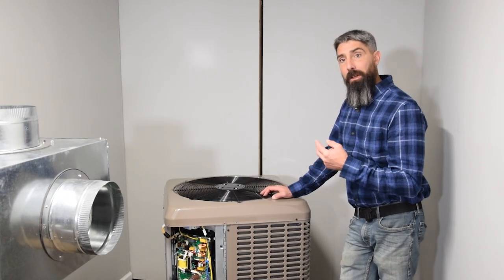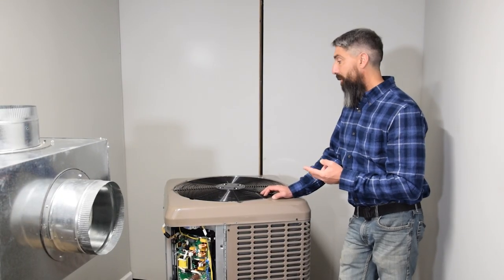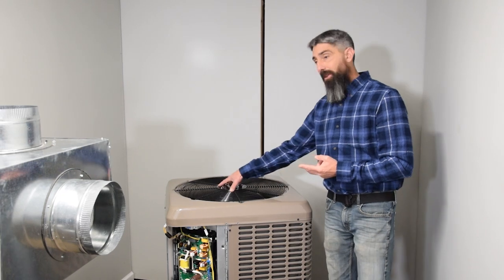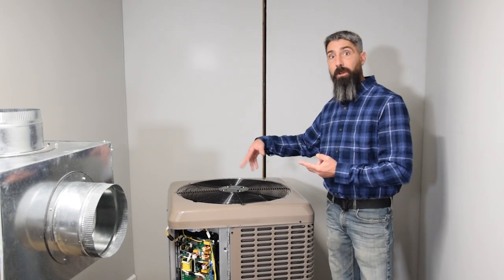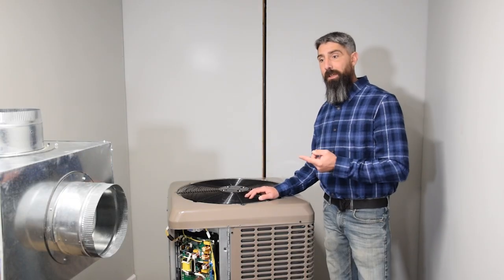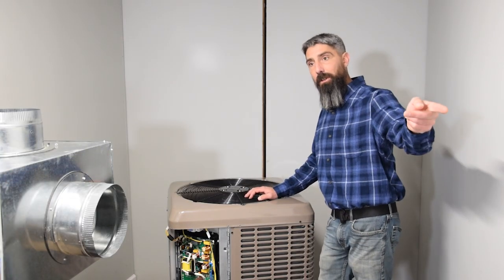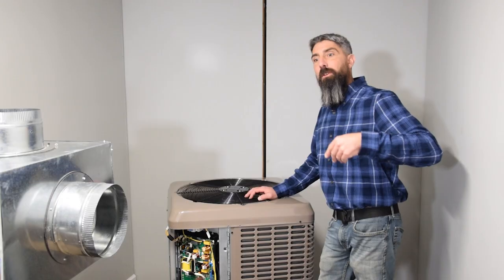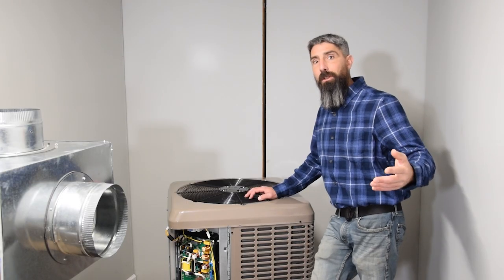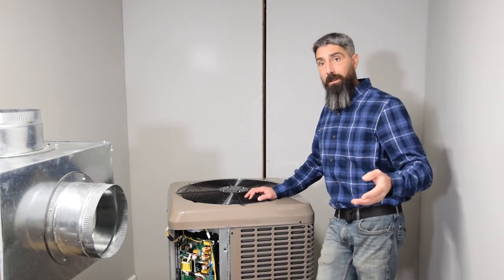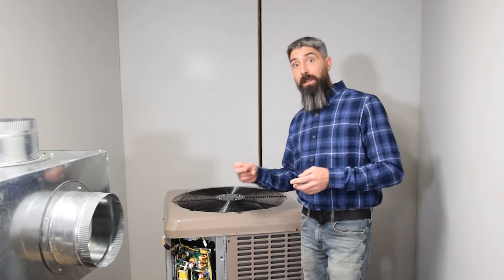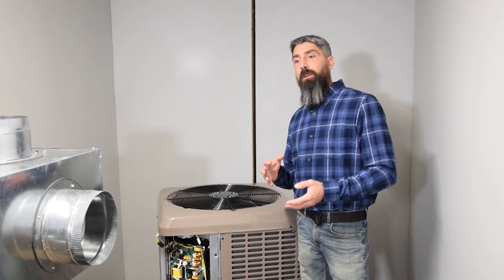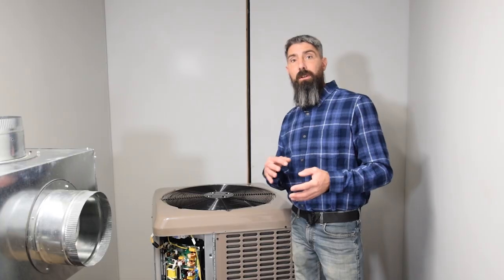Now it does another couple things to speed up that process. One of those things is this outdoor fan is going to shut off. So that outdoor fan, you'll notice that it quits spinning. And the third thing that's going to happen is it's going to send a signal to your indoor unit, your air handler, to bring on the auxiliary heat strips. It does that because it's switching to the cooling cycle. So you are going to notice immediately that now you have a not so warm air coming out of your vents.